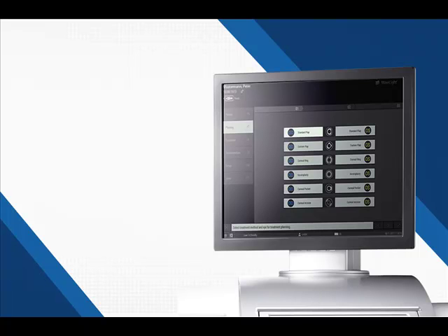For slide 23, not that it's wonderful or perfect, but I've kind of tried to put this together. What is the commonality for the competitors' patient interface, and what is soft-fit interface? Competitors all use liquid. The interfaces range from small to large. On the large side, you have to worry about Asian eyes or cutting the eyelid. Because it's all based on liquid, you have to worry about eye movement and misdirected shots.